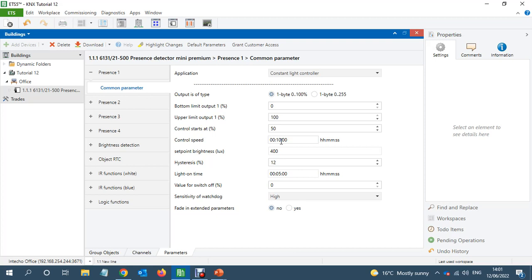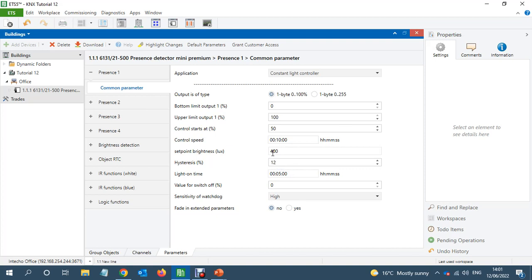What happens is if you got switches working parallel to the PIR, then this time, this 10 minutes sometimes causes problems. But we don't need to worry about that. Leave it 10 minutes, 10 minutes is fine.